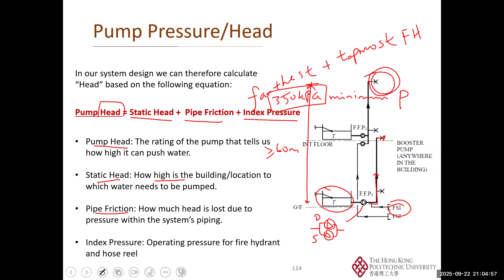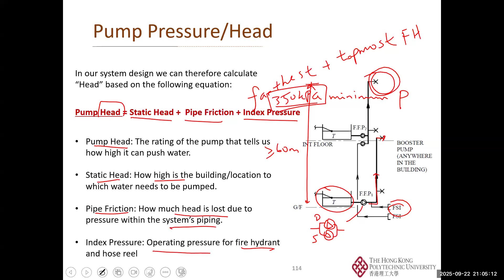The pump head is usually considered with the static head, friction loss, and index pressure, with the farthest and topmost point being the critical case, for example a fire hydrant. The pump head must ensure we have, for example, 350 kPa available at the hydrant minimum pressure. Static head is how high the building is. Friction loss is how much head is lost due to friction throughout the piping. Index pressure is the pressure at the hydrant or hose reel. As mentioned, 350 kPa is the minimum head required at the hydrant.